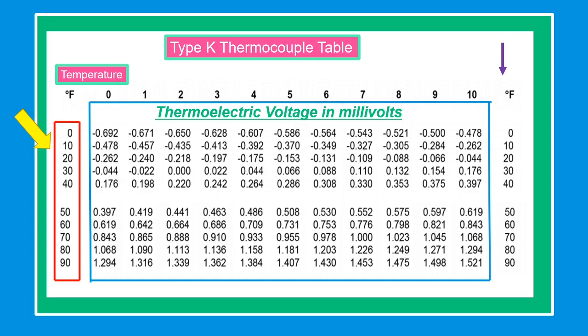Now, let's proceed to our thermocouple chart. In the left-hand column that I marked are the temperatures, can be either degrees Celsius or degrees Fahrenheit, and it is tens or hundreds. And on the top horizontal number, from 0 to 10, are ones for temperatures to be accurate. And on the inside value are thermoelectric voltage in millivolts.